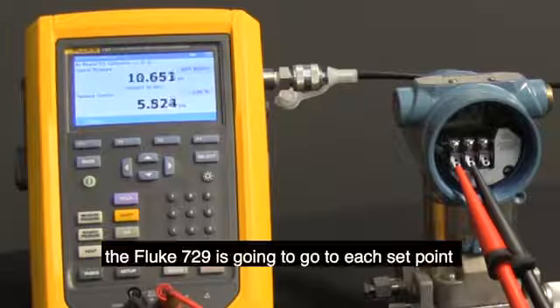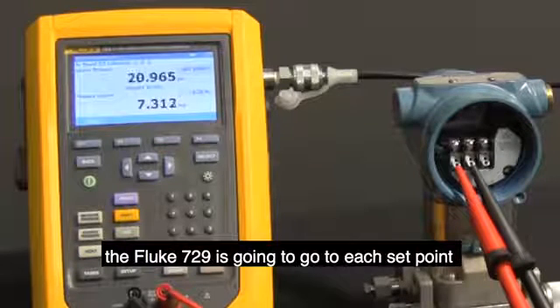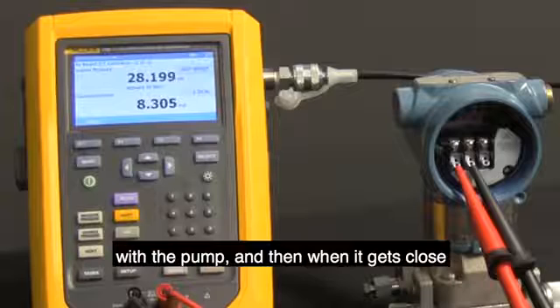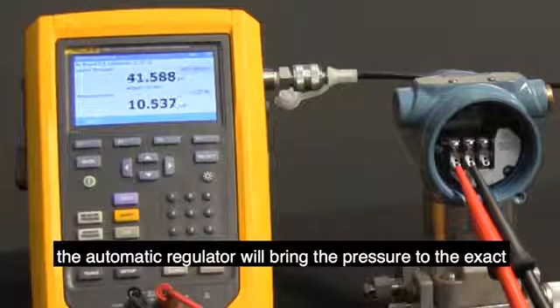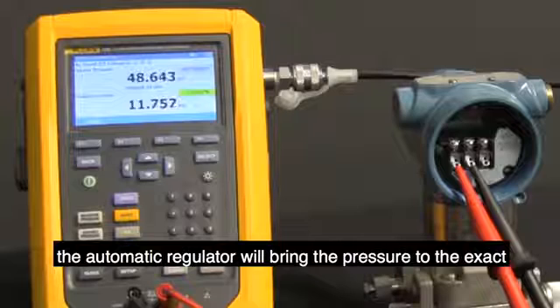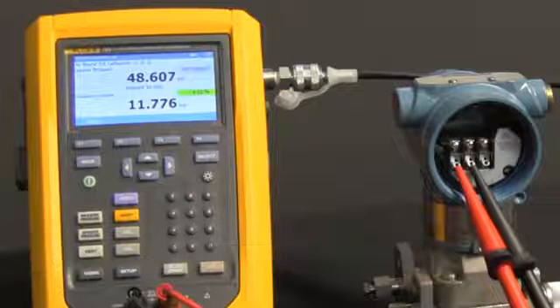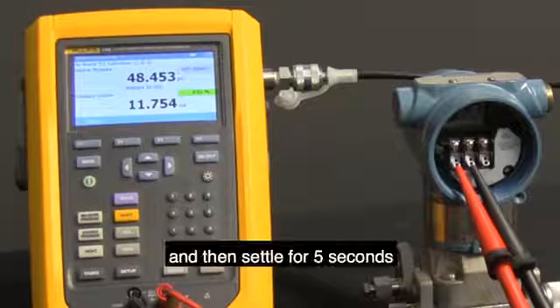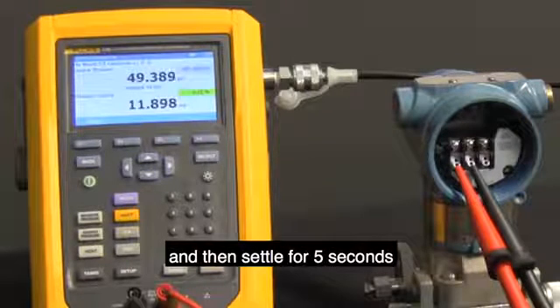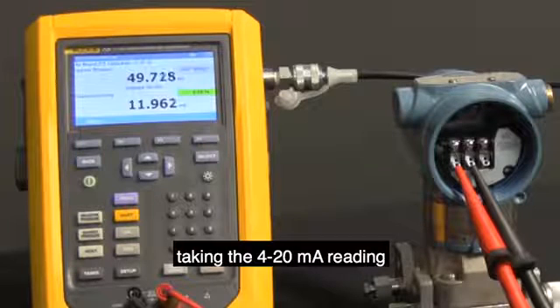The Fluke 729 is going to go to each set point with the pump, and then when it gets close, the automatic regulator will bring the pressure to the exact 50 psi setting in this particular test spot, and then settle for 5 seconds, taking the 4 to 20 milliamp reading.